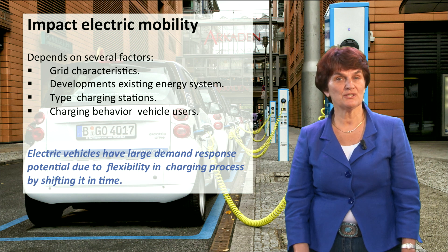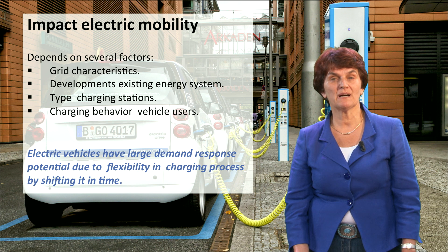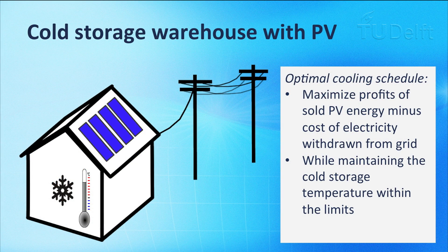Many other types of loads have this ability too. As an example of another type of responsive demand, a cold storage warehouse can be given. A cold storage warehouse is basically a huge refrigerator where goods are stored at very low temperature. Suppose for this illustrative example that the cold store has PV production on the same site and it can withdraw power from the grid and feed it back. In many countries, and presumably even more so in the future, tariffs for consuming are higher than for delivering energy to the grid. The challenge is to find the optimal cooling schedule that minimizes the total cost of cooling by maximizing the profit of solar PV energy minus the cost of electricity withdrawn from the grid while maintaining the cold storage temperature within the limits.